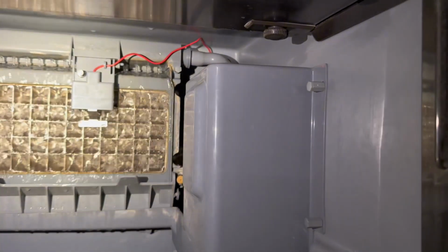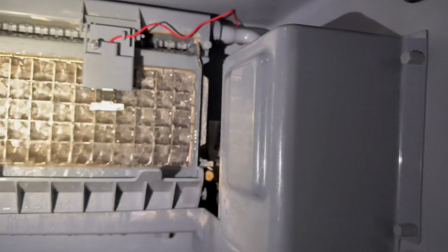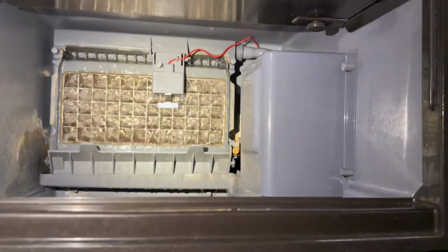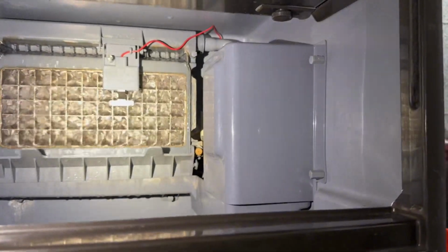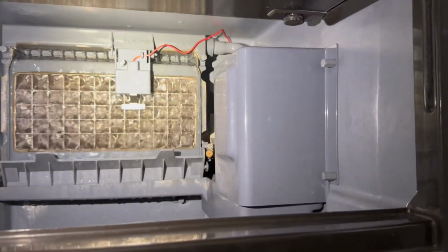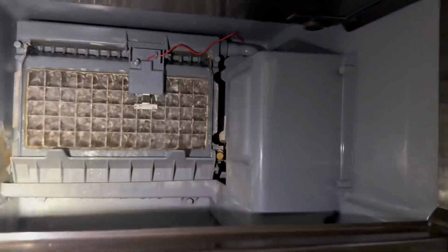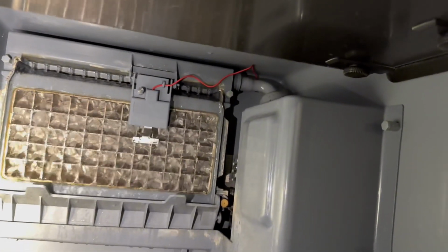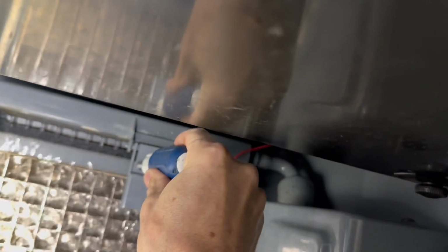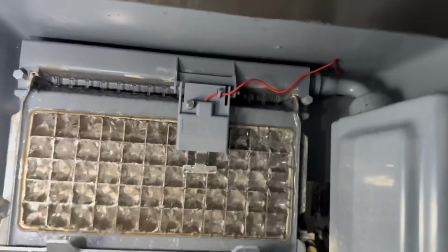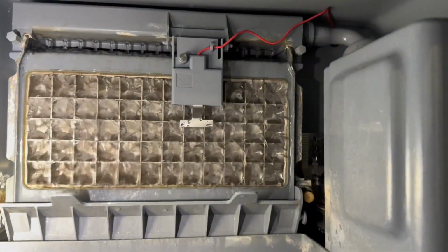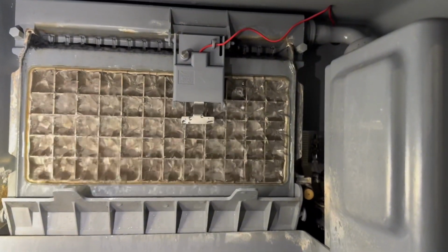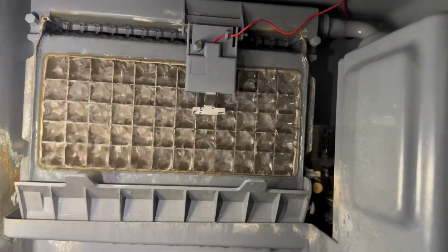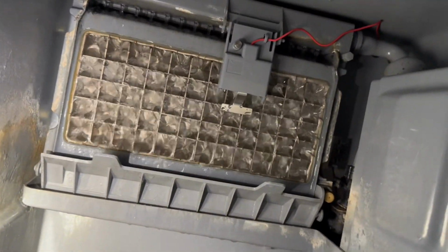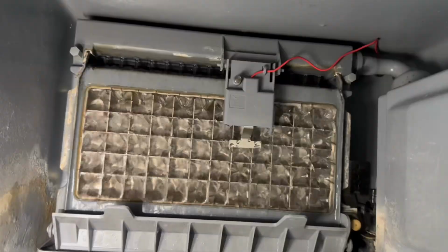We are at 21 minutes freeze time. We have a solid sheet of ice. My ice thickness probe still hasn't triggered my harvest yet, so I'm going to slowly take some thickness off of that probe, just using a 5/16. And I'm going to go counterclockwise, and then I'm going to do small quarter turns, and then wait 10 seconds in between each one until harvest is triggered.